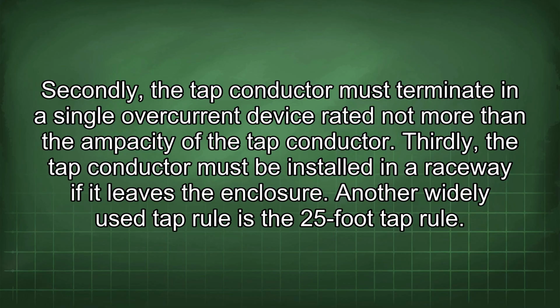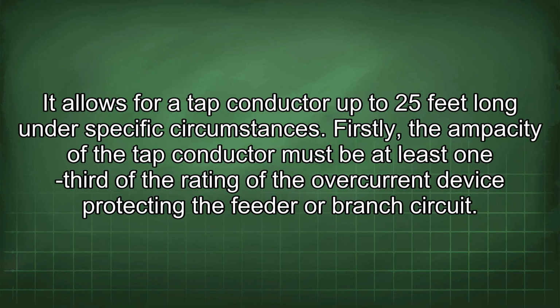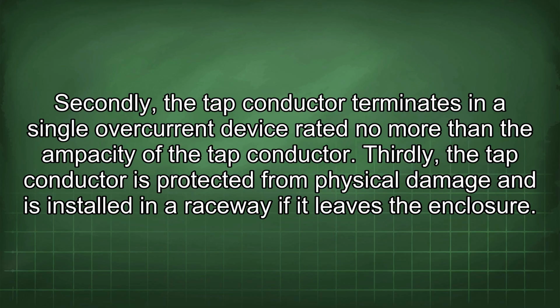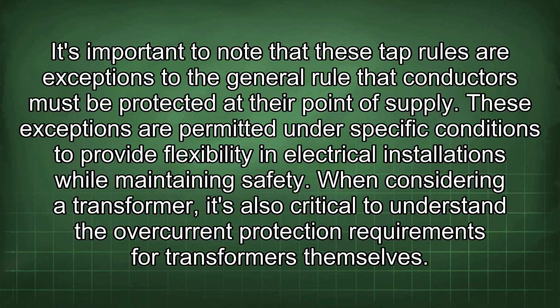Another widely used tap rule is the 25-foot tap rule. It allows for a tap conductor up to 25 feet long under specific circumstances. Firstly, the ampacity of the tap conductor must be at least 1/3 of the rating of the overcurrent device protecting the feeder or branch circuit. Secondly, the tap conductor terminates in a single overcurrent device rated no more than the ampacity of the tap conductor. Thirdly, the tap conductor is protected from physical damage and is installed in a raceway if it leaves the enclosure. It's important to note that these tap rules are exceptions to the general rule that conductors must be protected at their point of supply. These exceptions are permitted under specific conditions to provide flexibility in electrical installations while maintaining safety.